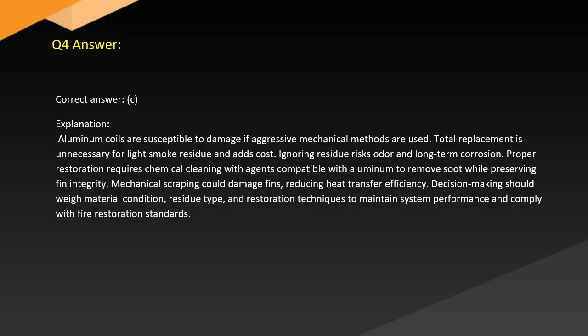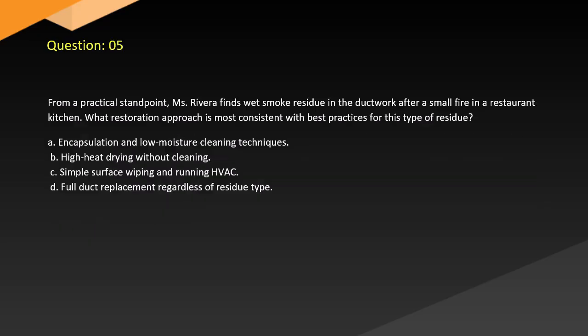Aluminum coils are susceptible to damage if aggressive mechanical methods are used. Total replacement is unnecessary for light smoke residue and adds cost. Ignoring residue risks odor and long-term corrosion. Proper restoration requires chemical cleaning with agents compatible with aluminum to remove soot while preserving fin integrity. Mechanical scraping could damage fins, reducing heat transfer efficiency. The decision should weigh material condition, residue type, and restoration techniques to maintain system performance and comply with fire restoration standards.